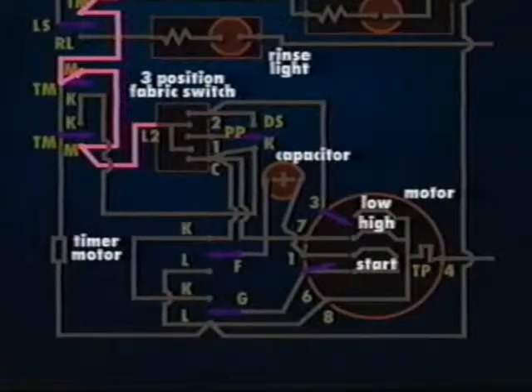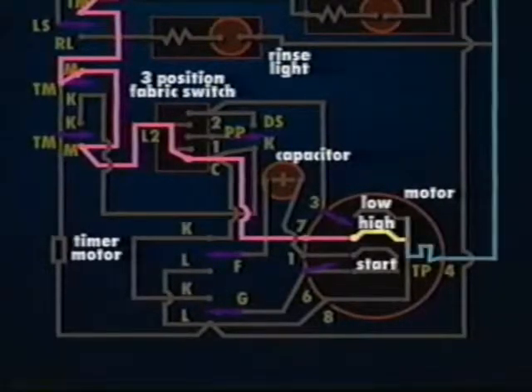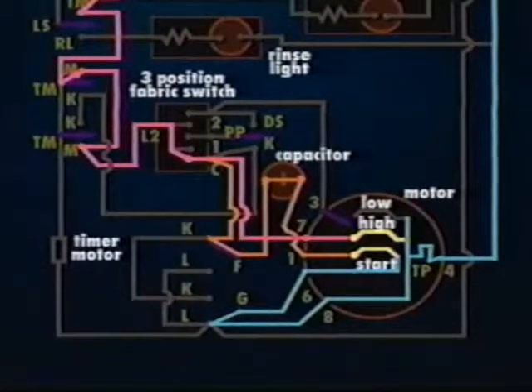Set on the normal selection, L2 to C provides the path to the high winding. The neutral side of the high winding is made through the thermal protector. Line 1 is also routed through K to F and the start capacitor to the start winding. The neutral side of the start winding is made from the thermal protector through L to G in the timer. With voltage across both windings, the motor will start and run. A centrifugal switch in the motor opens the start winding circuit once motor RPM is achieved.